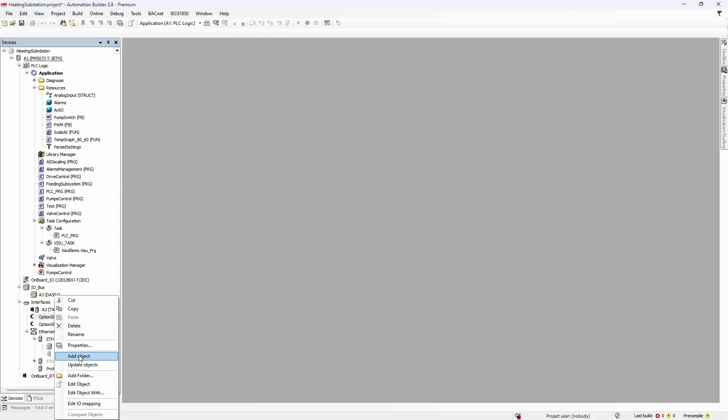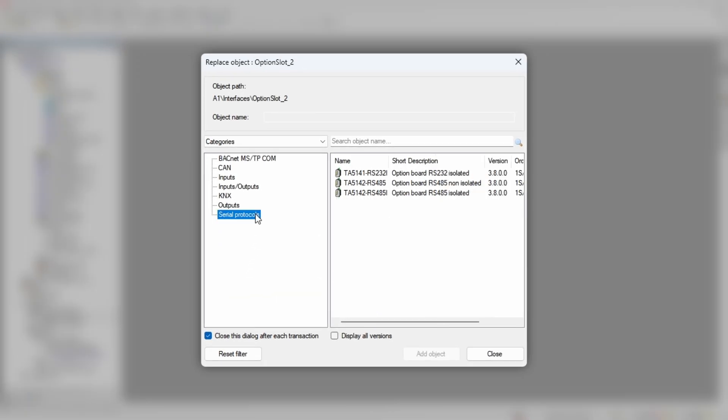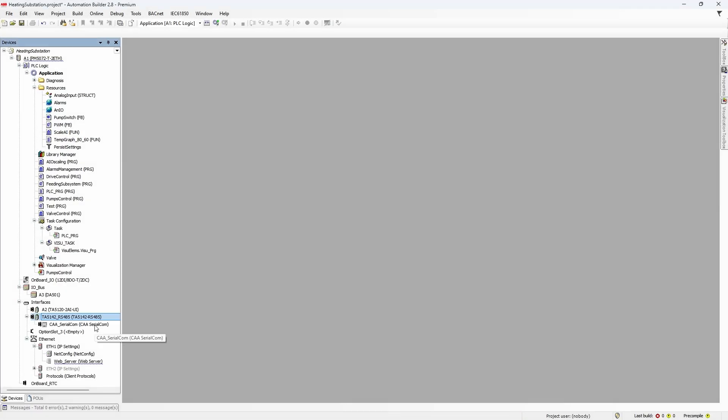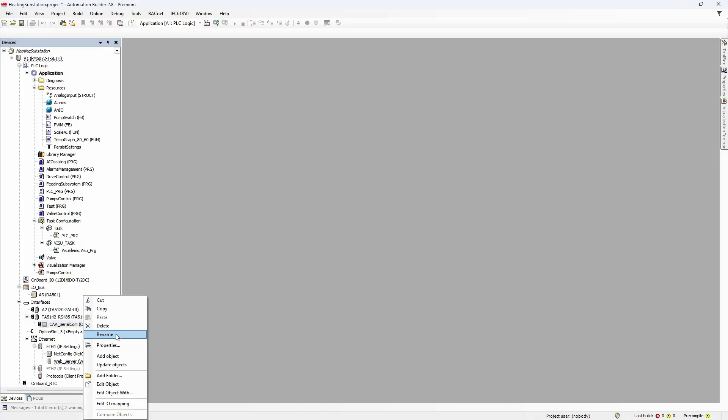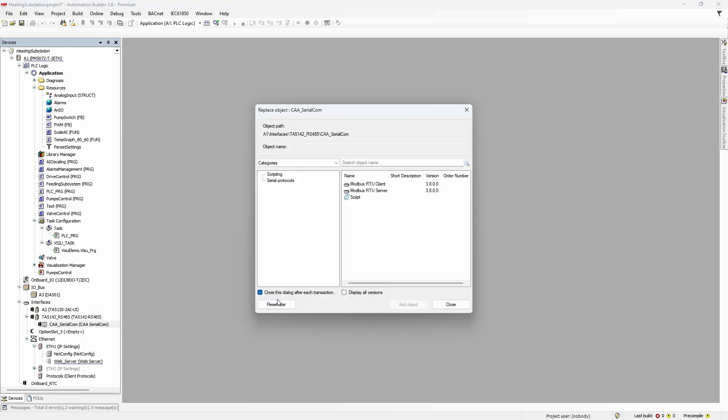Now it's time to jump to PLC configuration. Find option slot 2 and add a new object to it. Select the category serial protocols and then one of the RS485 options. Go to the settings of the added option board and make sure that parameters like baud rate, parity, and data/stop bits are the same as in the drive configuration. Next, right-click on serial COM and add a Modbus RTU client — in other words, the PLC will act as Modbus master on this serial line.